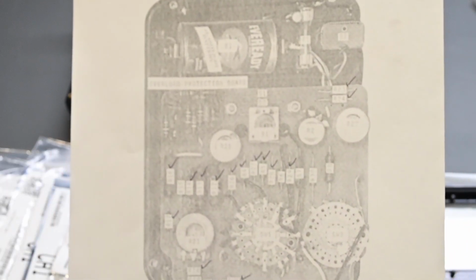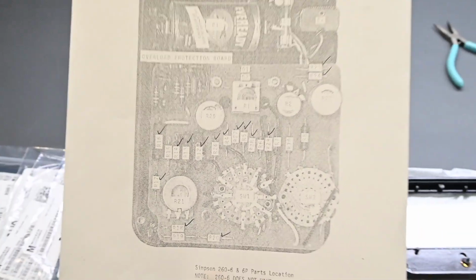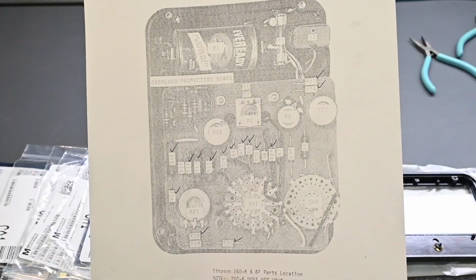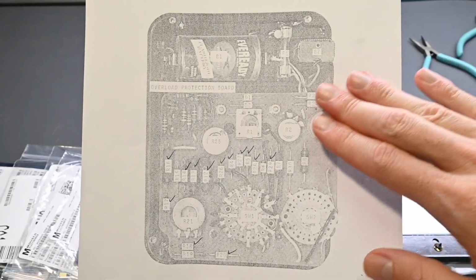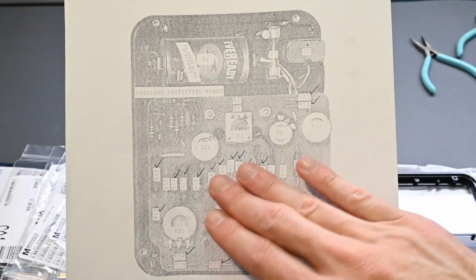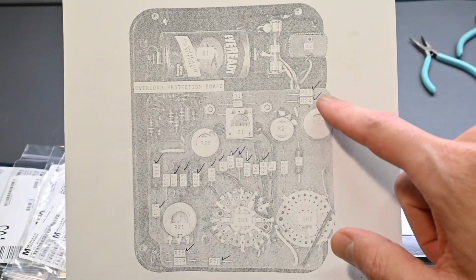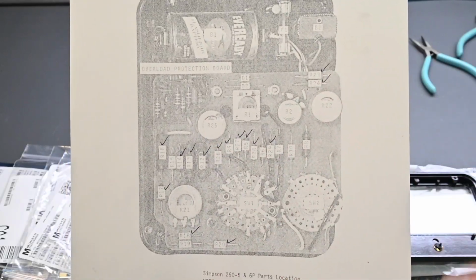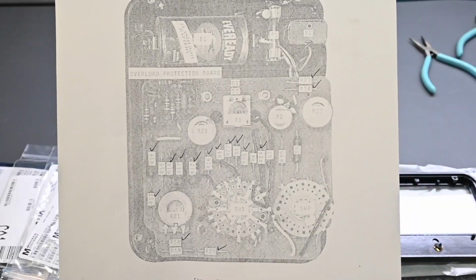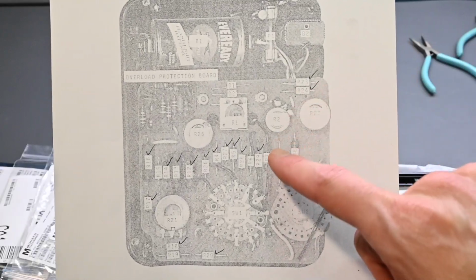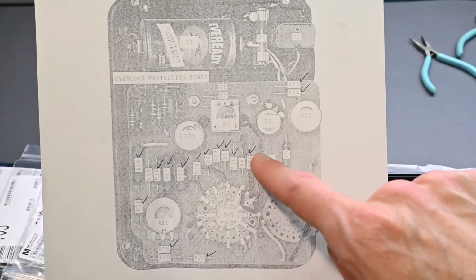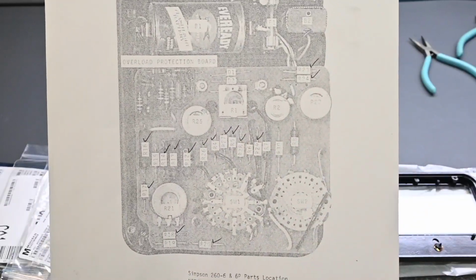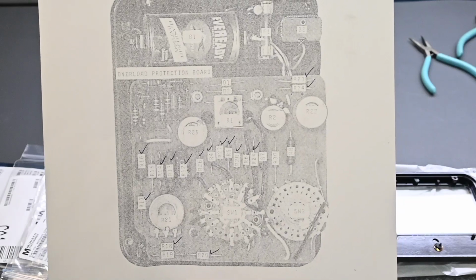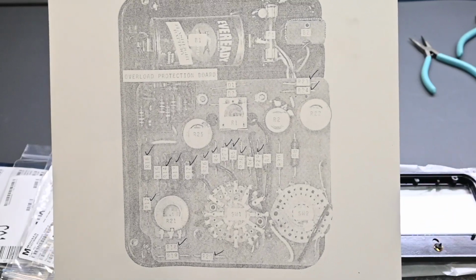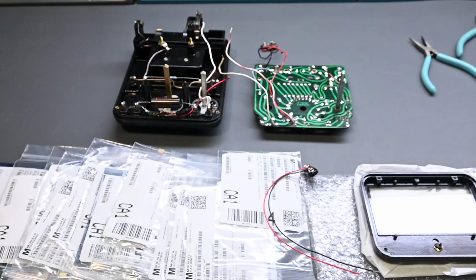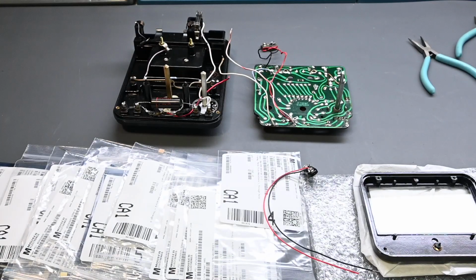So this is out of a service manual. Get this so you can see the whole thing here. And after I went through all of the resistors, the obvious ones where they've been overheated and damaged, of course, need to be replaced. But I took a measurement on every resistor in here, and they're all supposed to be 1% tolerance. But I found that many of these resistors that looked okay, especially down through here, the multiplier resistors, they were actually out of tolerance, so they had drifted beyond the 1%. And the idea with this meter is to make the meter as accurate as possible and something that I can use on the bench for troubleshooting.